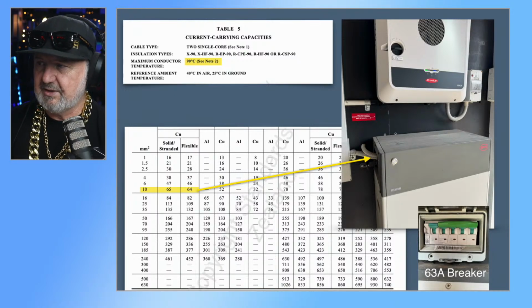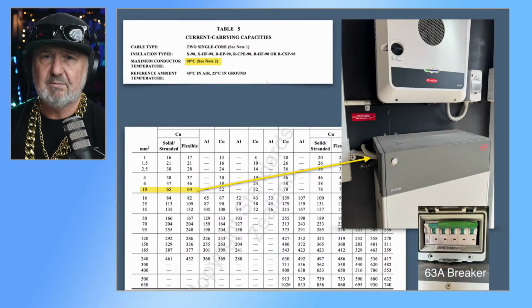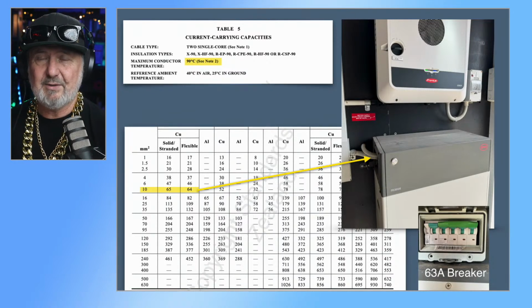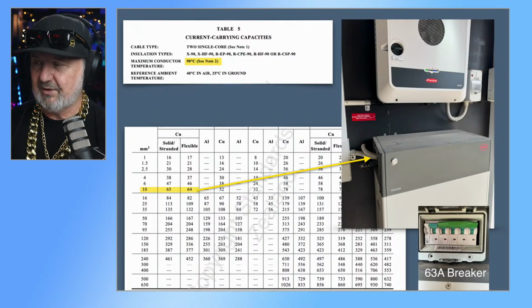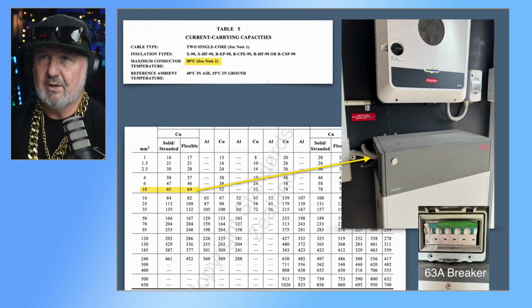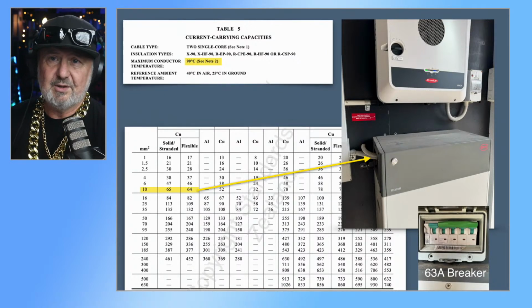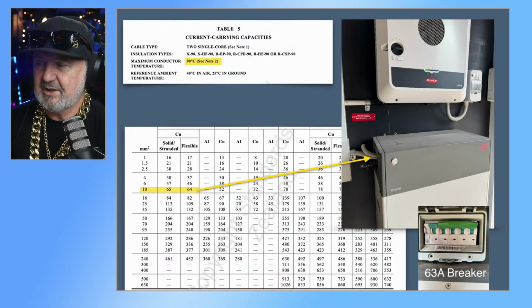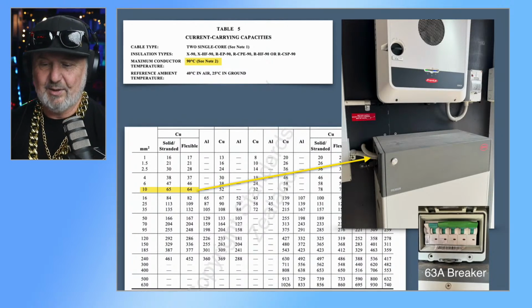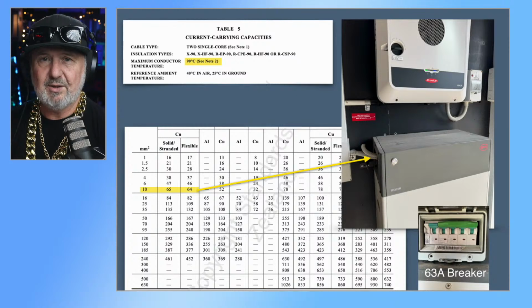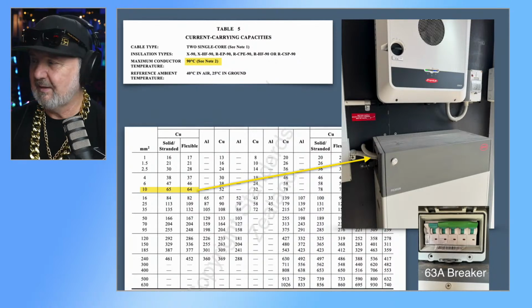And so we had to go and find some high temperature rated cable. We used some Huber+Suhner, I think it was 110 degree rated, and we found that 10 mil could do the trick. So 10 mil cable, not a little bit of 6 mil. Often you'll find battery systems come with substandard cable sizes as standard. You need to confer with, or check with AS/NZS 3008 that they are suitable for the application, and particularly when you consider derating. So in this case, this column is for cables enclosed in conduit touching a surface, which is pretty much what we've got there, and they rated a 10 mil cable flexible at 64 amps. So we just squeezed in with 1 amp to spare. So there you go. So make sure that you do your due diligence for cable selection based on the overcurrent protection device built into the battery system, and not just assume that the manufacturer has provided you with the right stuff. Do your due diligence.